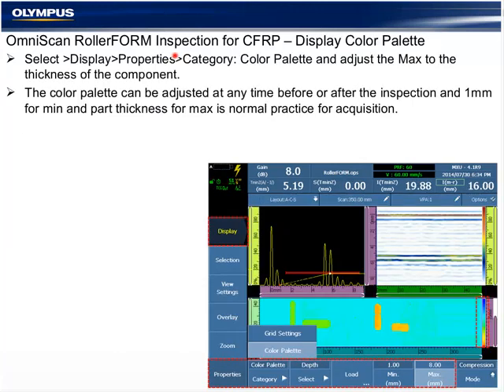Continuing on to the display color palette, select Menu Display, Submenu Properties, Color Palette Depth, and by default we'll see the same scale here. In the previous slide, that min-max range controlled the purple ruler on the UT reading here, and this will scale the color palette over that value from red to blue. And that can either be a compression or exclusion mode.